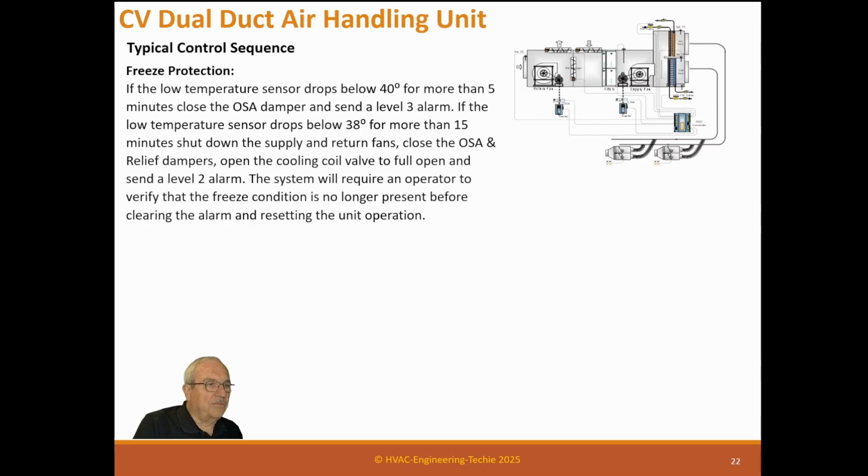The system will require an operator to verify the freeze condition is no longer present before clearing the alarm and resetting the unit operation. So now you can use this, this is the cold temperature here. It's going to tell us we're going to freeze alarm. That we want to prevent that.